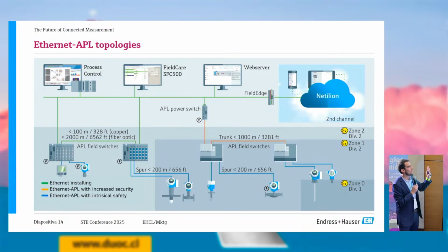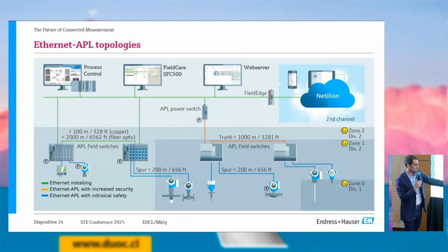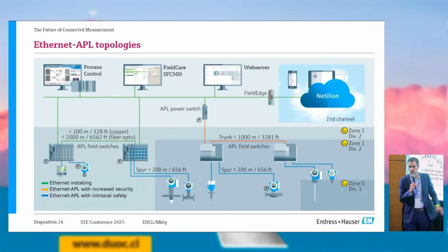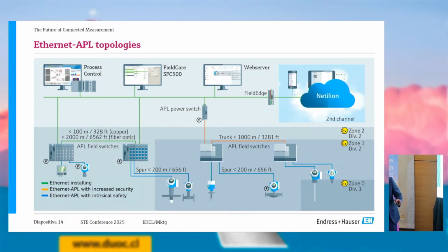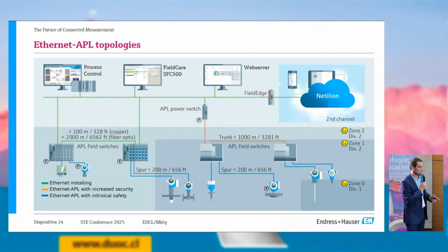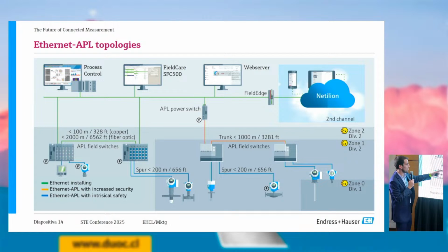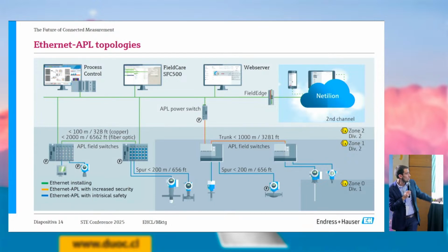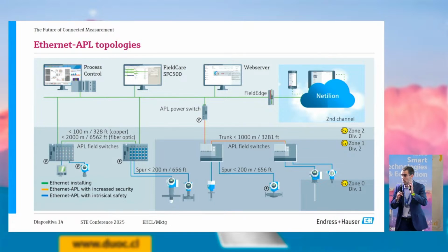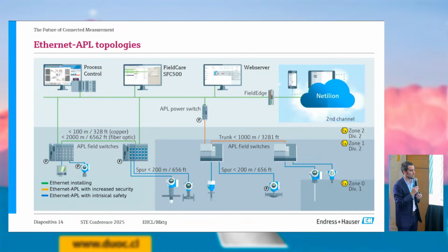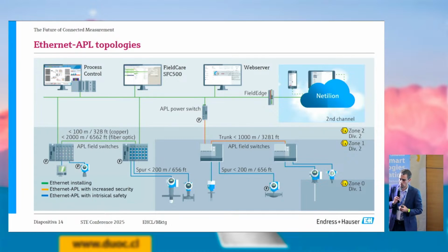Here's a general overview of a topology where, at the moment, with Ethernet APL with intrinsic safety, you get support up to 200 meters. That's quite good. But the most interesting part is that with this two-wire Ethernet installation, you can even find fiber optic options. It says 2 kilometers, but as far as I understand now, it's 32 kilometers, with lower coverage, but anyway, we're increasing the chances to go beyond that with Ethernet through this project.